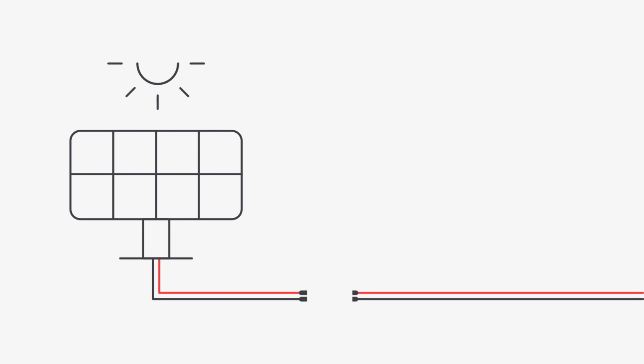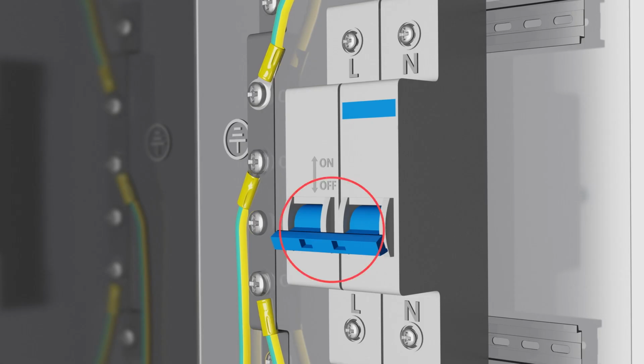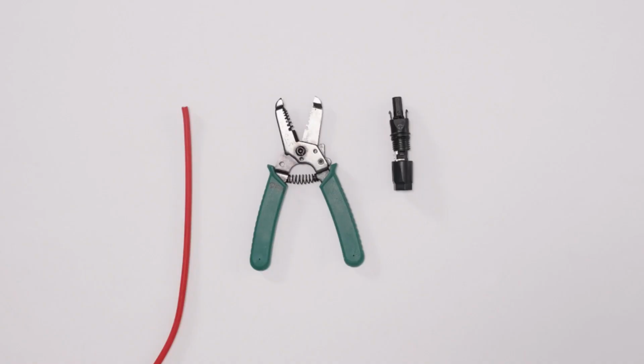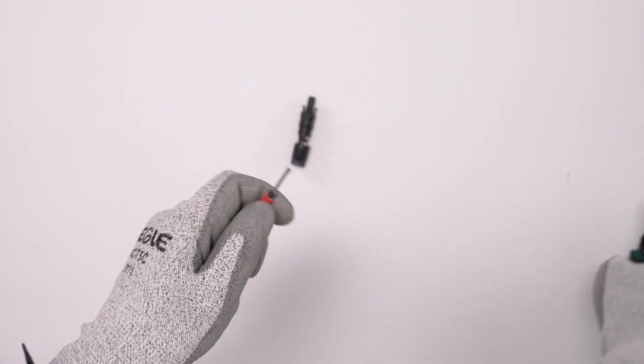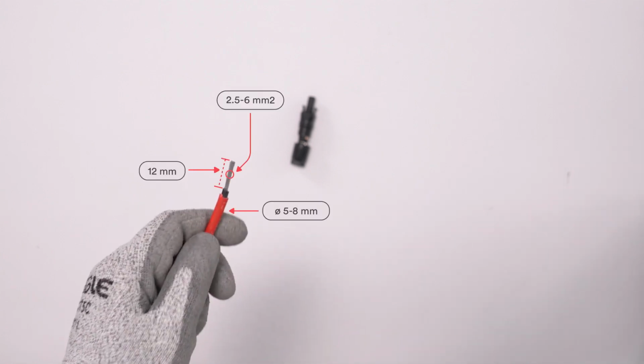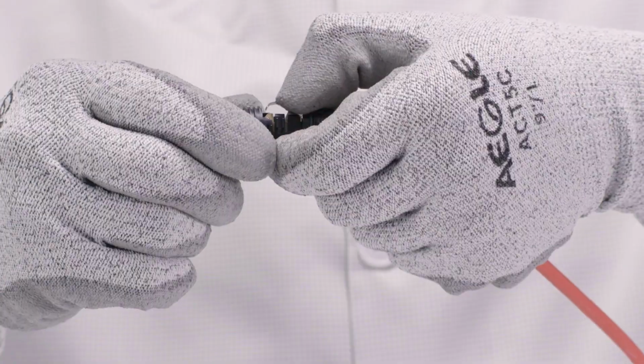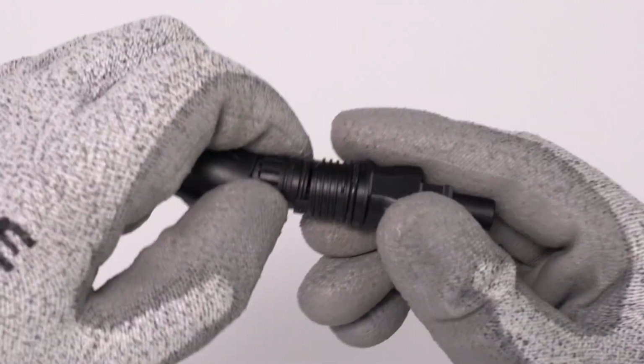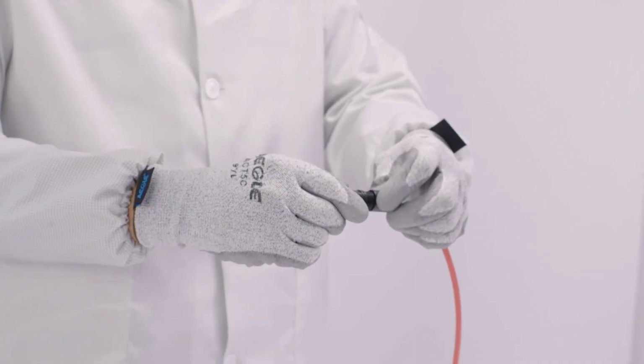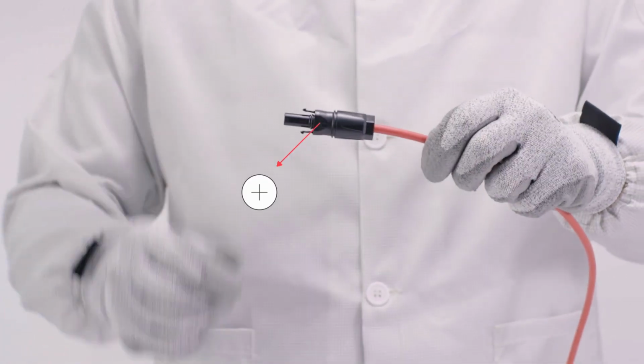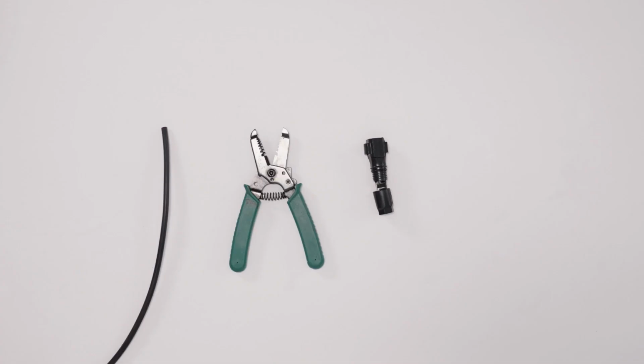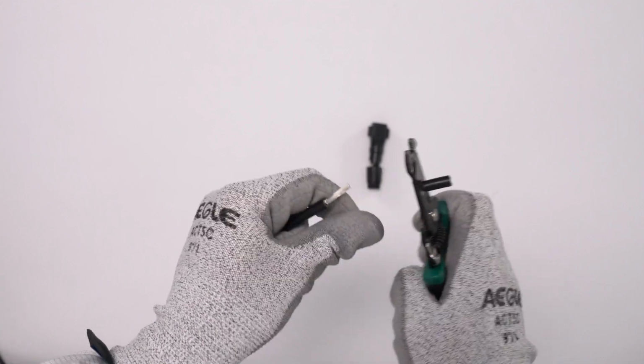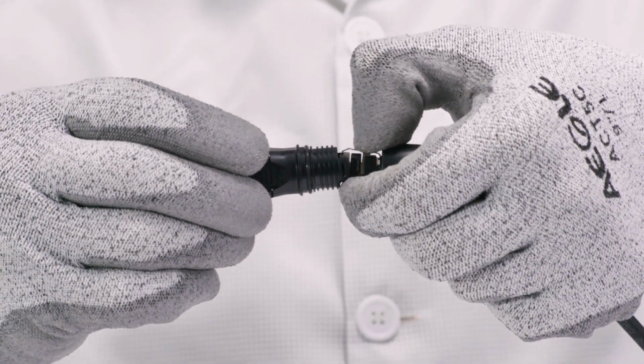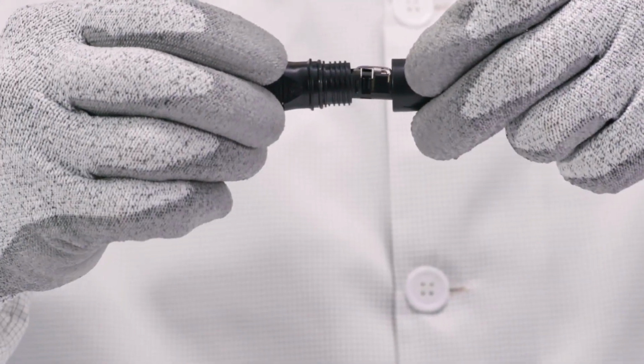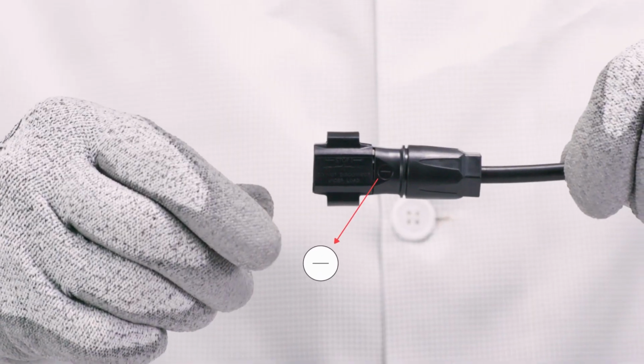Disconnecting the PV array. Make sure the AC circuit breaker is disconnected and the DC switch is in the off position before stripping 12 mm off the cable insulation. Route the stripped cable all the way into the DC connector. Ensure that the stripped cable and the DC connector have the same polarity. Press the clamping bracket down until it audibly snaps into place. Ensure that the cable is correctly positioned. Push the swivel nut up to the thread and tighten.